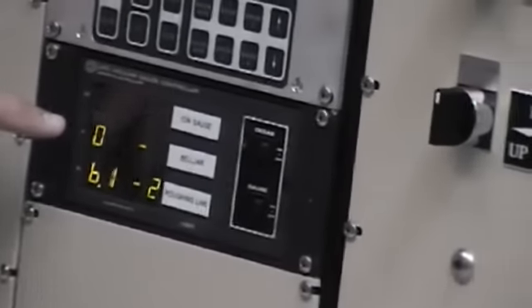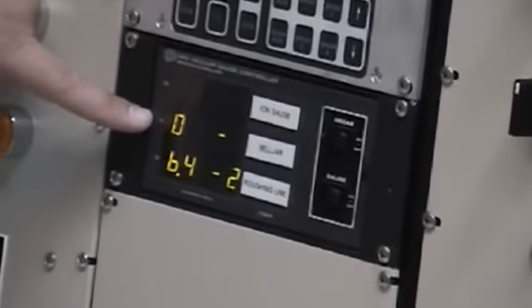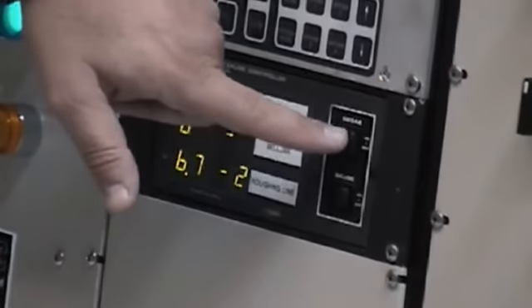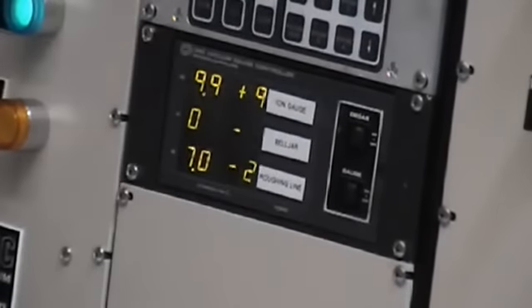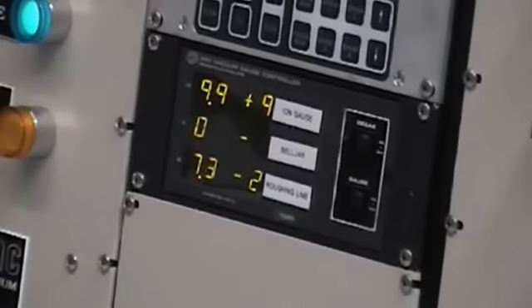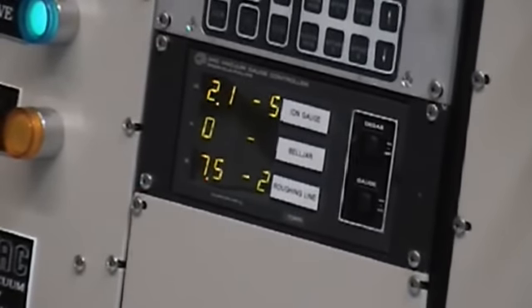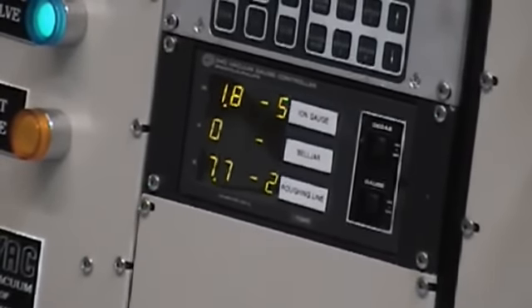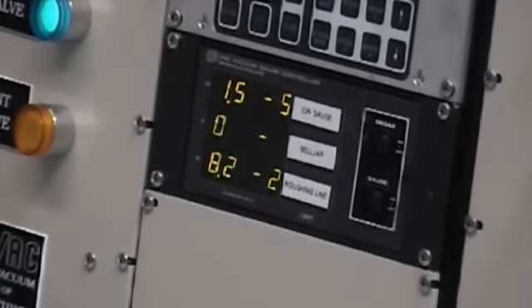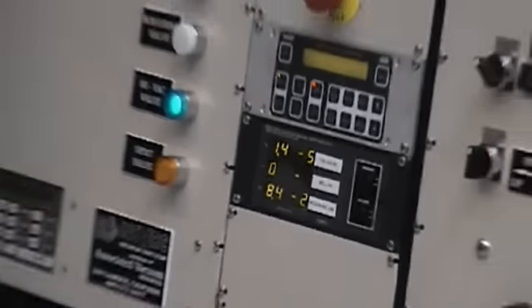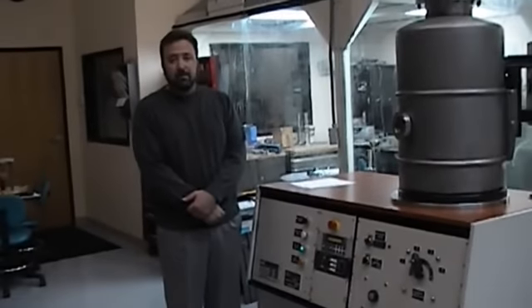We are now at high vac, as witnessed by the bell jar convectron, which is now at 0. We will turn on the high vacuum ion gauge and see that it quickly is at 1.5 times 10 to the -5. That pressure should rapidly go into the 6.